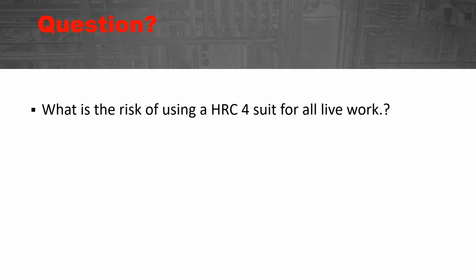Charlie, this is a great question. If it's the older arc flash suit, category 4, it has to be rated for at least 40 calories per square centimeter of incident energy. It has to have at least that much arc rating. A risk with some of the older equipment is that it is heavy and bulky. If you've seen some of these suits, it looks like a bomb suit, like someone who's going to defuse bombs. Well, suits have gotten so much better. I mentioned Oberon. I like their products.